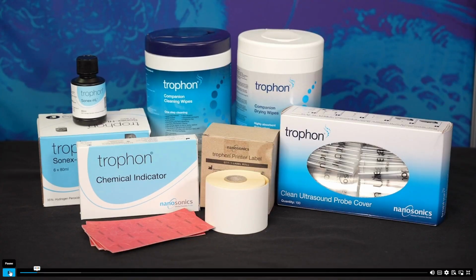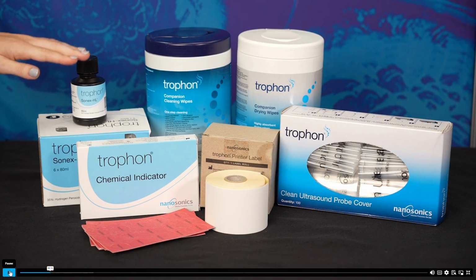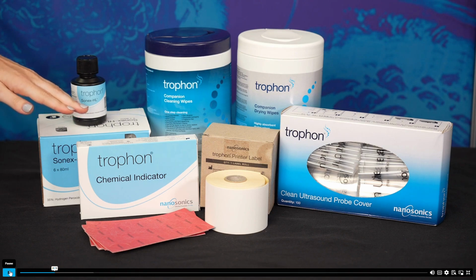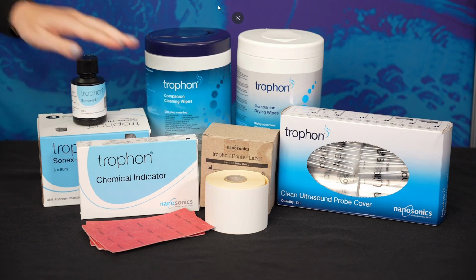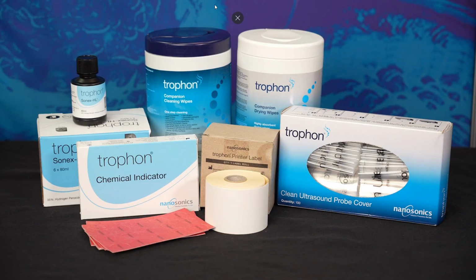The consumables required to run a cycle on the Trophon2 device include Sonex disinfectant cartridges, chemical indicators, and printer paper roll, if a printer was purchased. The Sonex disinfectant is a highly concentrated hydrogen peroxide solution. Each cartridge will yield approximately 20 to 40 cycles, depending on the frequency of use. Once a cartridge is loaded into the unit, it will expire in 30 days.